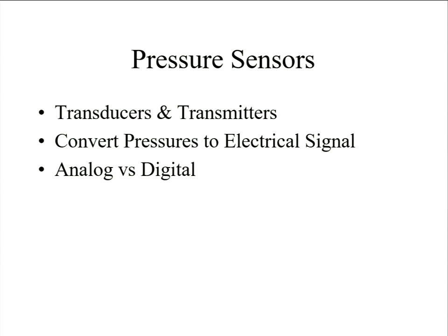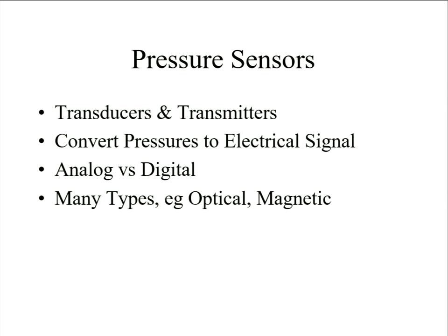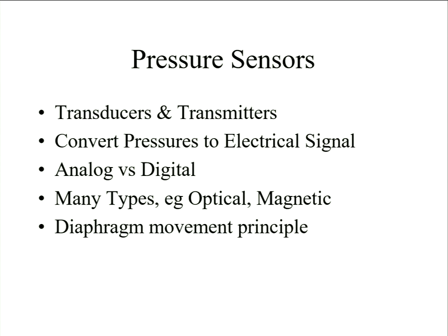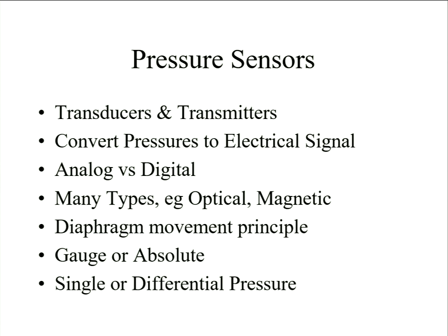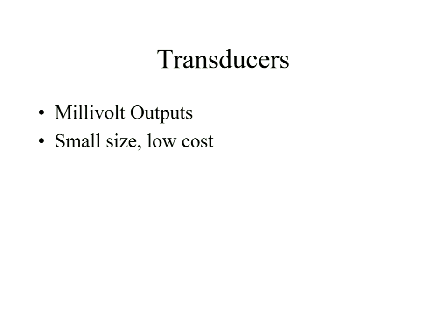Whereas transmitters, if you're working on bigger pipelines and process plant, you're probably really looking at this sort of stuff. So it might be 0 to 10 volts, but more typically current loop, 4 to 20 milliamps. And one advantage found with that is if somebody actually breaks the connection, you can tell. 4 milliamps will give you 0, 20 milliamps will give you 100%. If somebody actually pulls the wires out, or rats get into your cable ducting and eat through the insulation and short things out, and rats quite like cable ducting because they're a very nice pathway and they quite like eating plastic on occasions, if it goes to 0, you'll get effectively a minus 25% reading. So you know the difference between a fault and it genuinely reading 0 because the answer today is 0. So that's why 4 not 0.